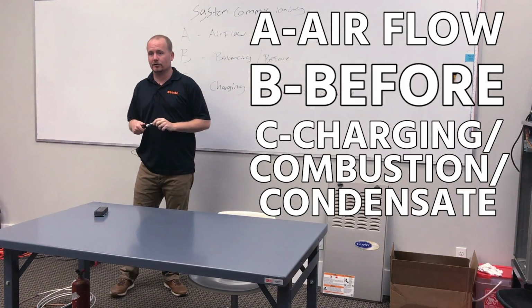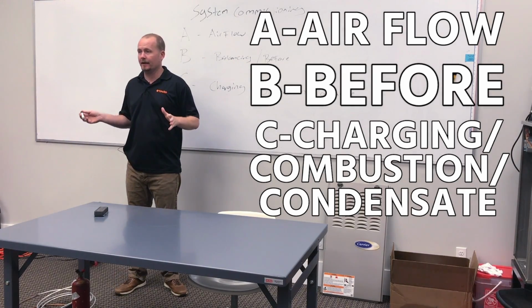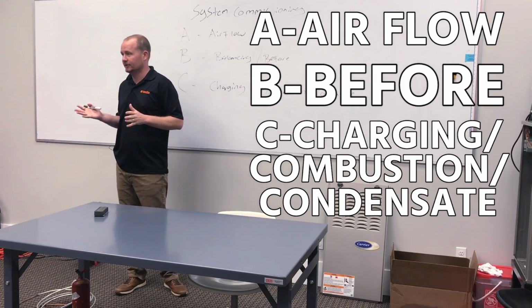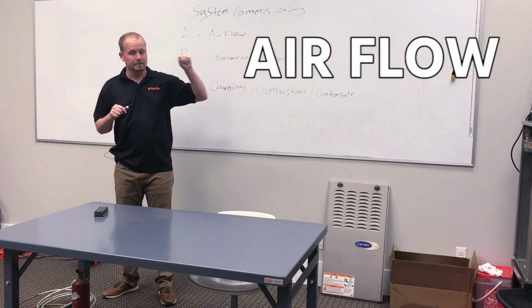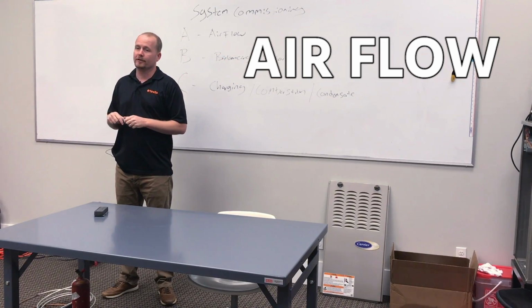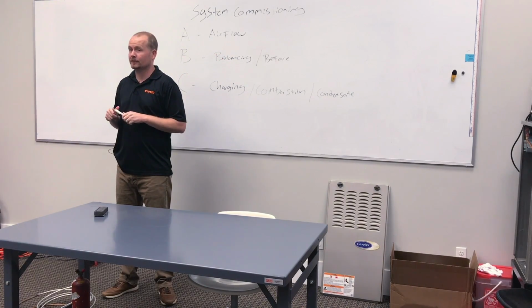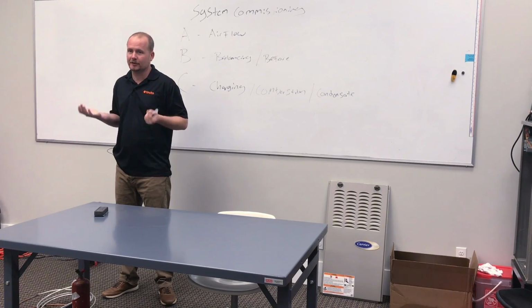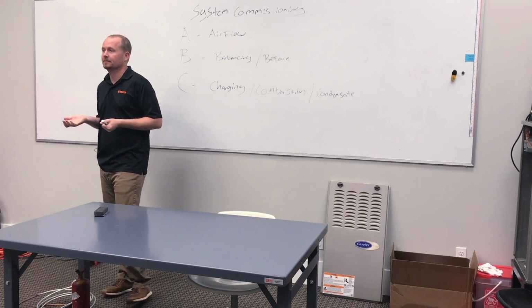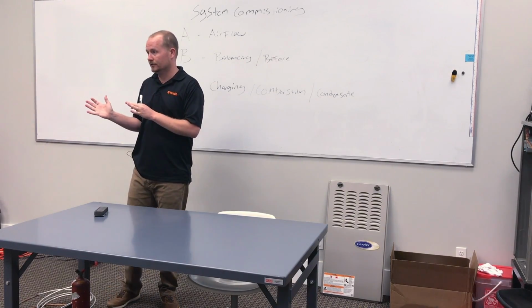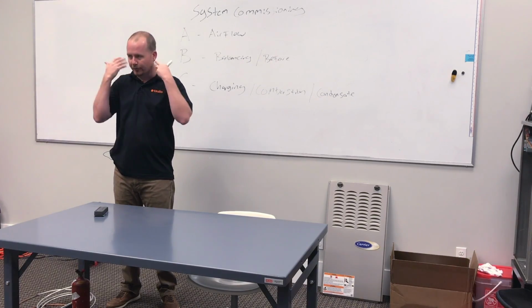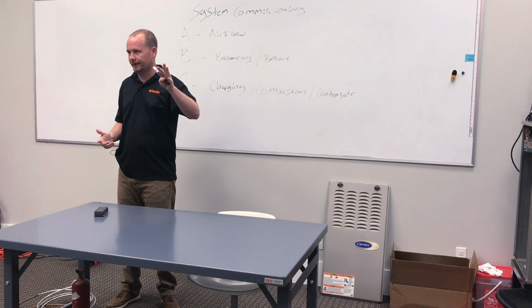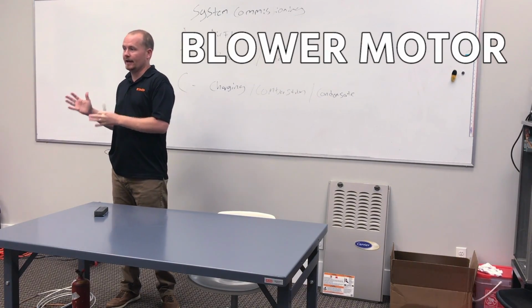Are we really checking airflow first? Are we thinking about airflow first? That's the question. So airflow, what is the first way that you confirm airflow when you're working on a system? No, really, what's really the first way you confirm airflow when you're working on a system? There are two different airflows. The one that you're going to focus on when you think of airflow is the blower motor, right? So if it's not running, then obviously you can't check the rest of the system.